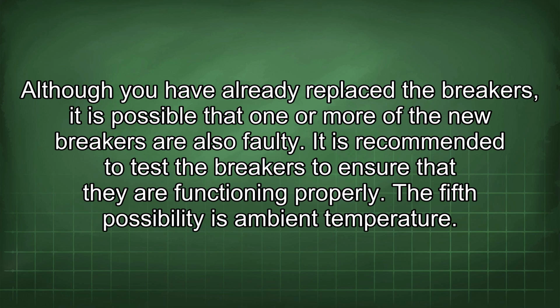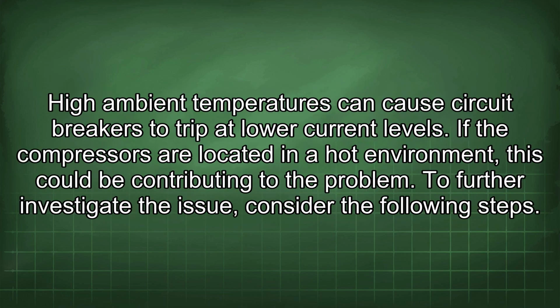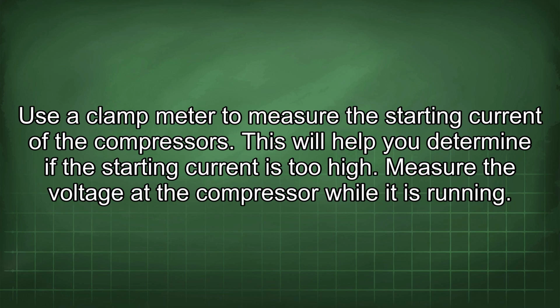The fifth possibility is ambient temperature. High ambient temperatures can cause circuit breakers to trip at low current levels. If the compressors are located in a hot environment, this could be contributing to the problem. To further investigate the issue, consider the following steps. Use a clamp meter to measure the starting current of the compressors. This will help you determine if the starting current is too high.